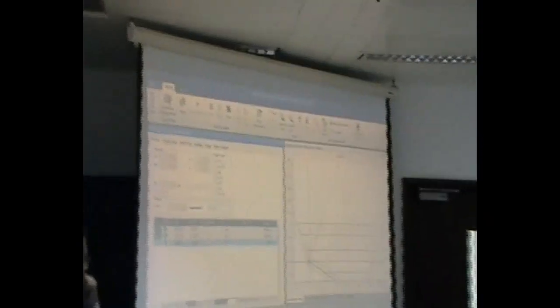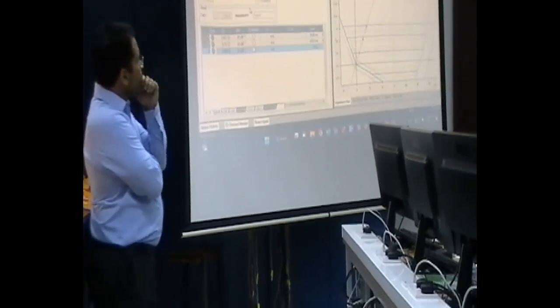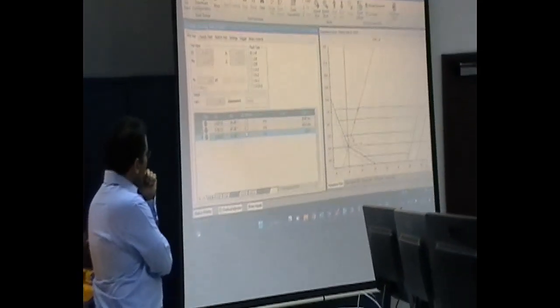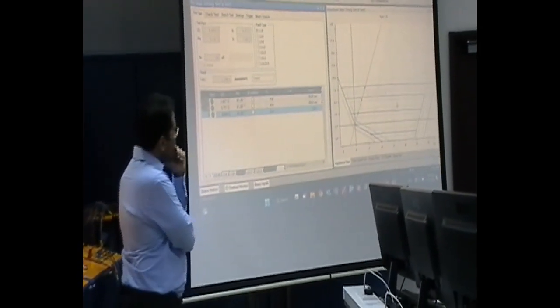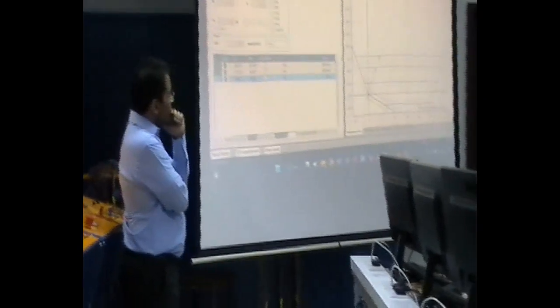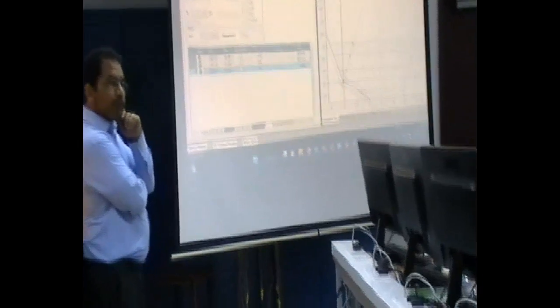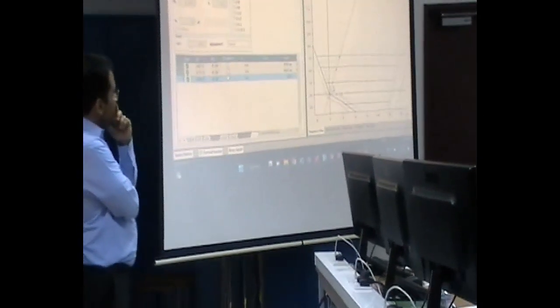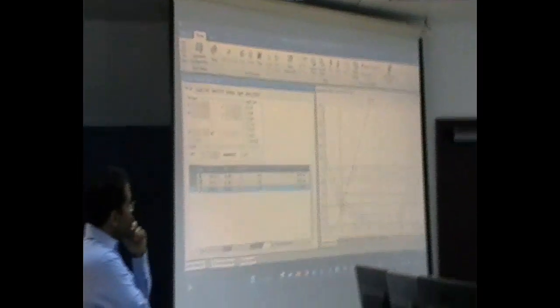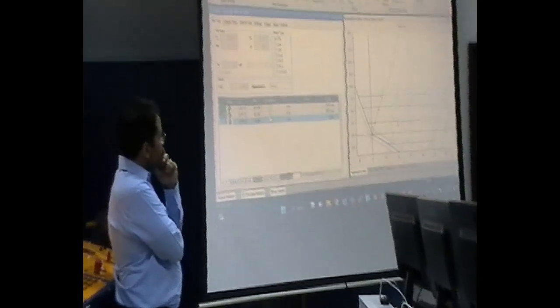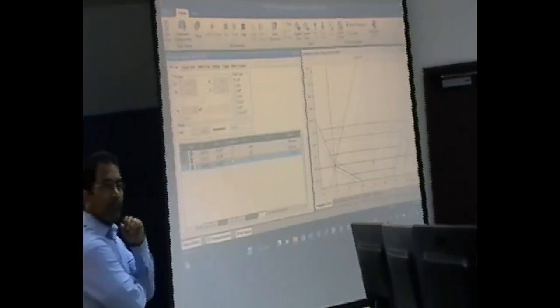For example, I could be injecting any type of fault, whatever I want. So here the first one is line to earth. I've selected some points in the zones. This zone is drawn based on the setting which I have already imported. So this is the setting, the characteristic of my relay. I have chosen three points in the line. I could be choosing anywhere inside the zone.